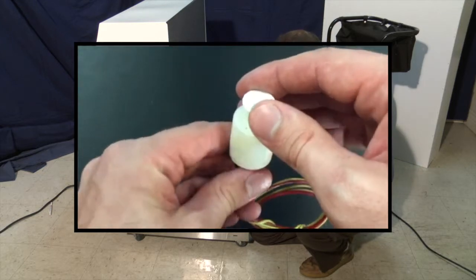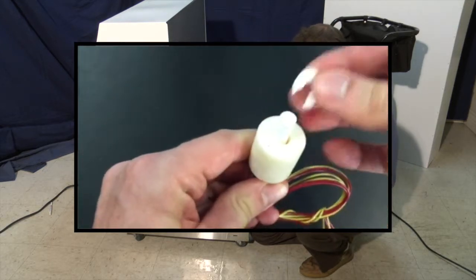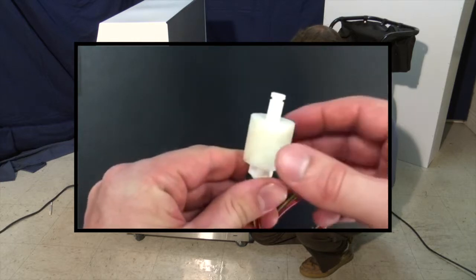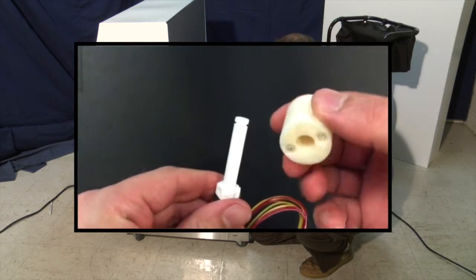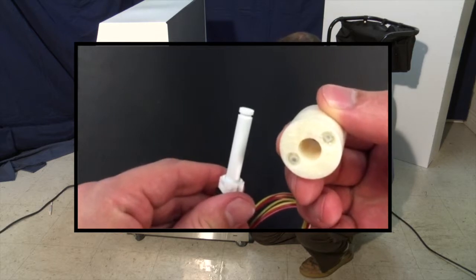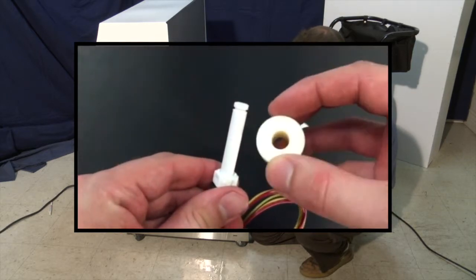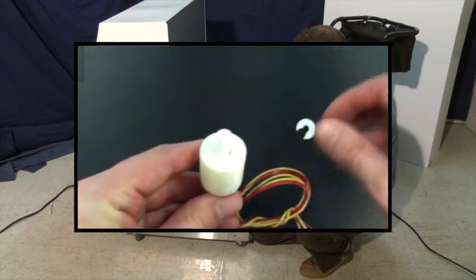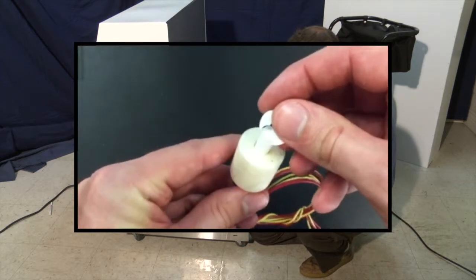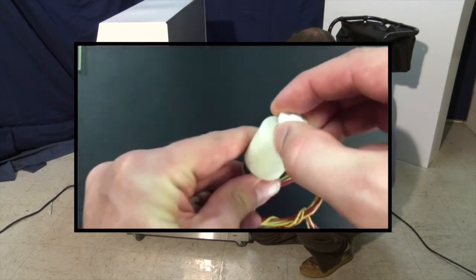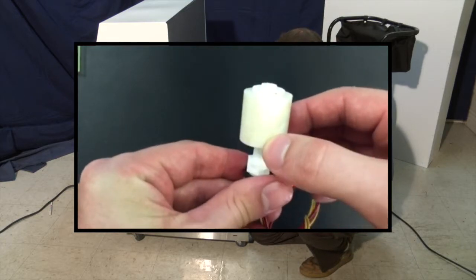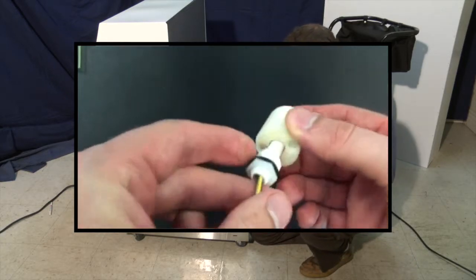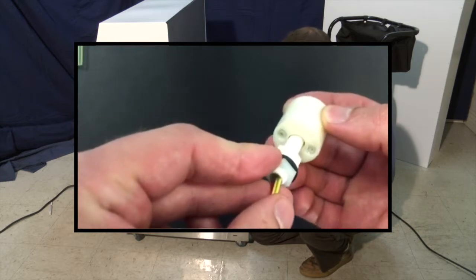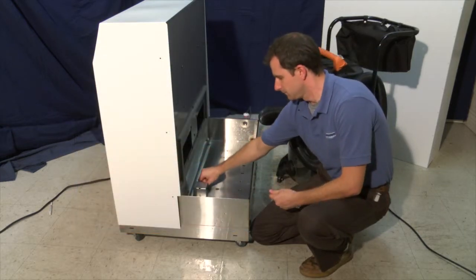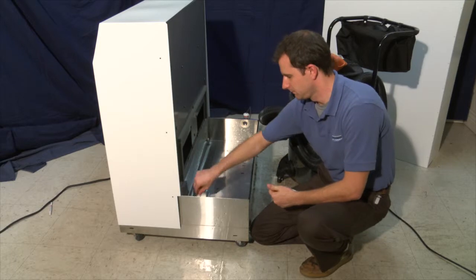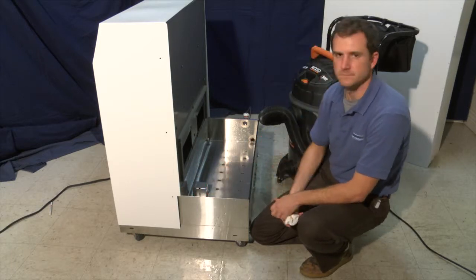You may remove the styrofoam stopper from the shaft in order to clean both thoroughly. However, be sure to note that there are two small magnetic discs on the bottom of the styrofoam stopper. You must ensure the magnetic discs are in the bottom position when reassembling your float. Also, be sure to secure the metal float house back in place. The float house ensures a stable water level for the float to measure.